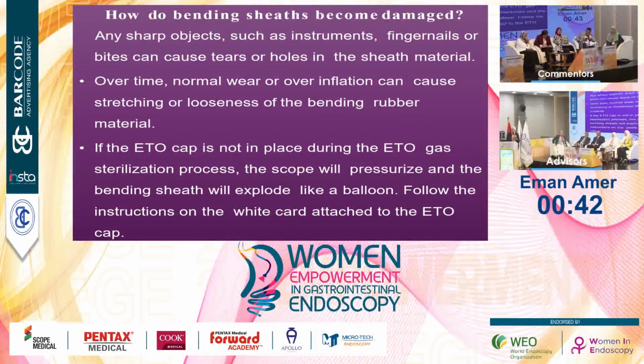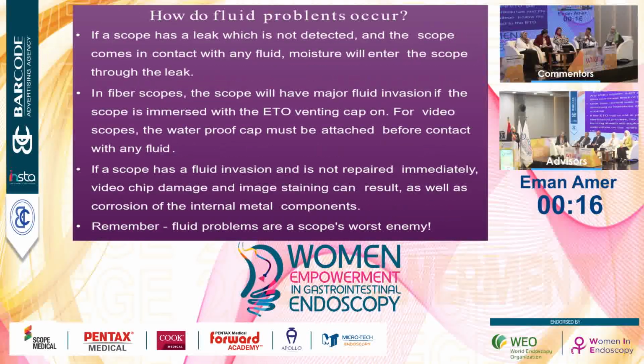How do bending sheaths become damaged? Any sharp object, such as instruments, fingernails, or bites, can cause tears or holes in the sheath material. That's why we put a mouthpiece in the mouth of the patient. Over time, normal wear or overinflation can cause stretching or loosening of the bending rubber material. If the ETO cap is not placed during the ETO gas sterilization process, the scope will pressurize and the bending sheath will explode like a balloon.